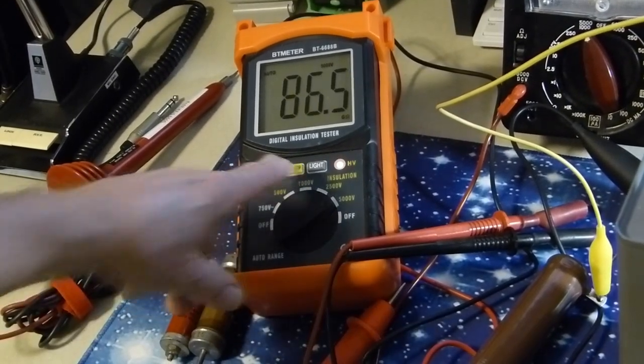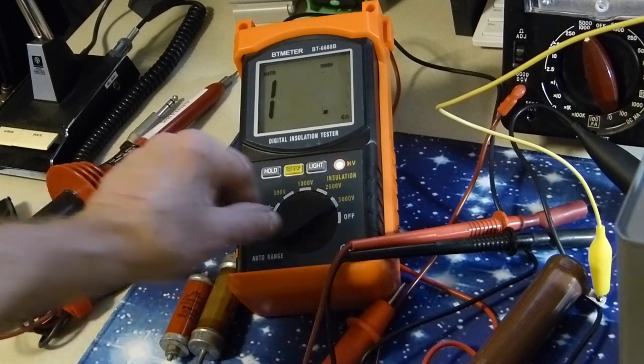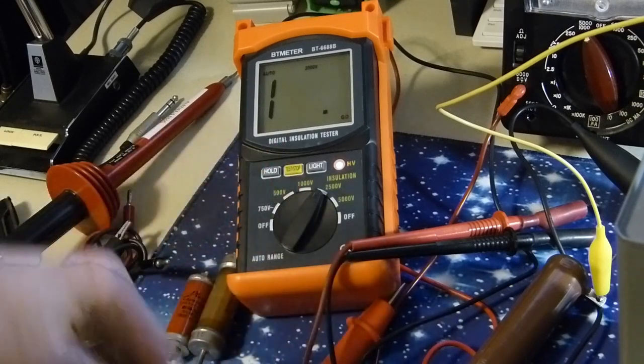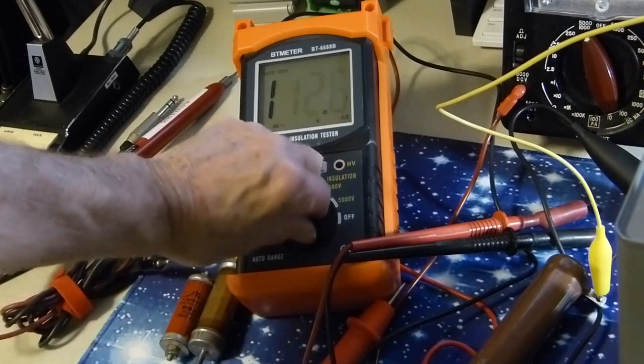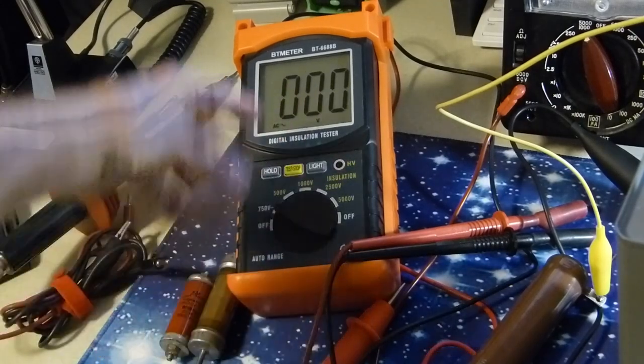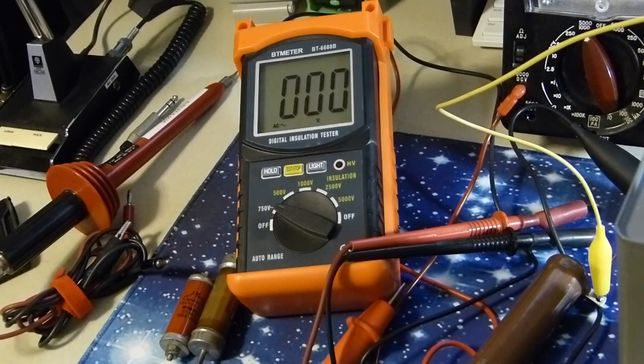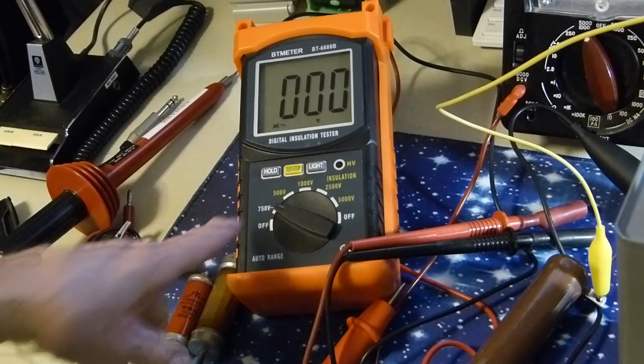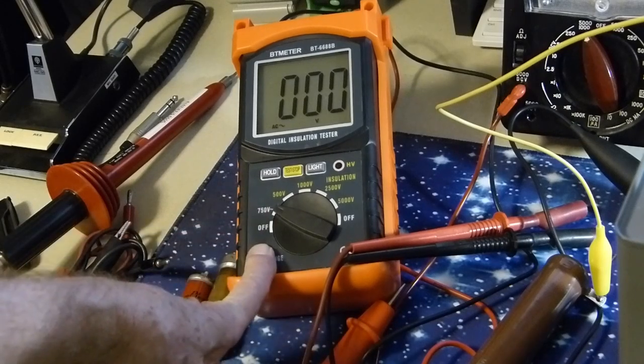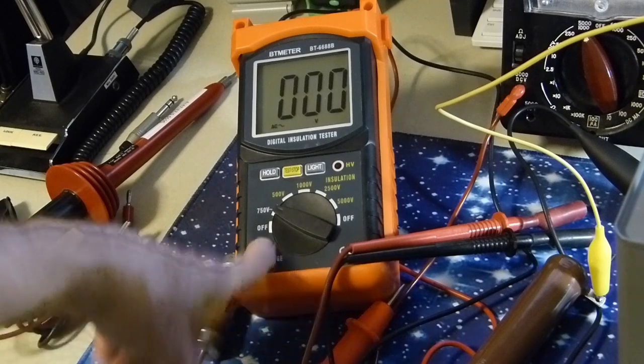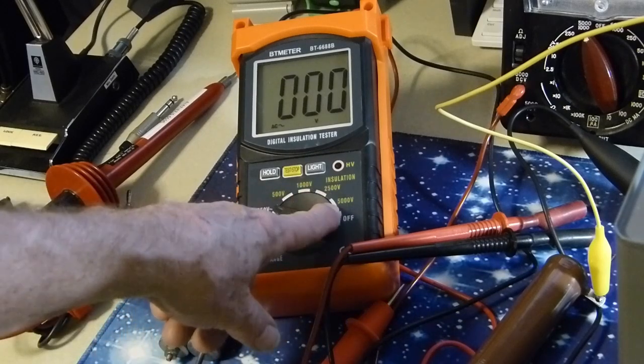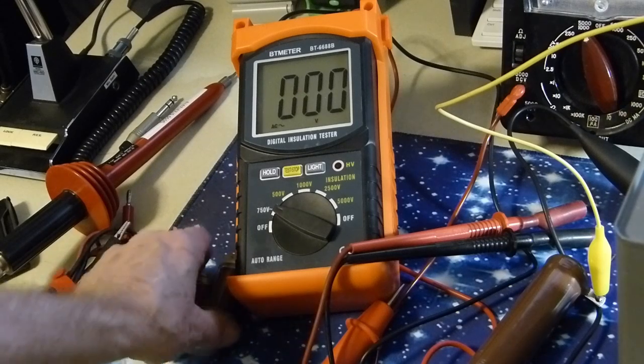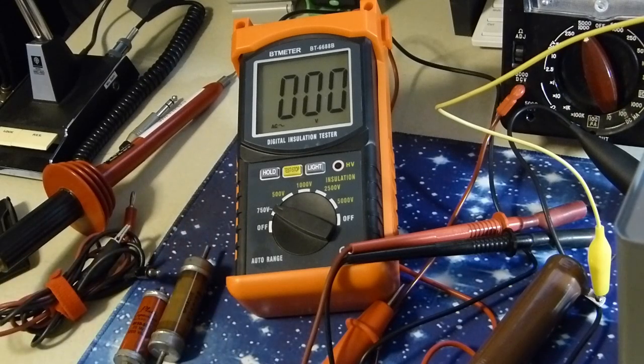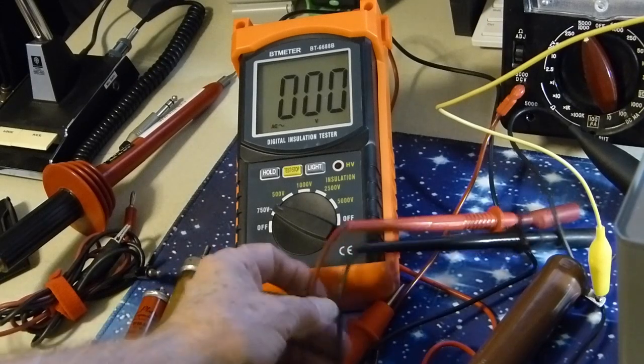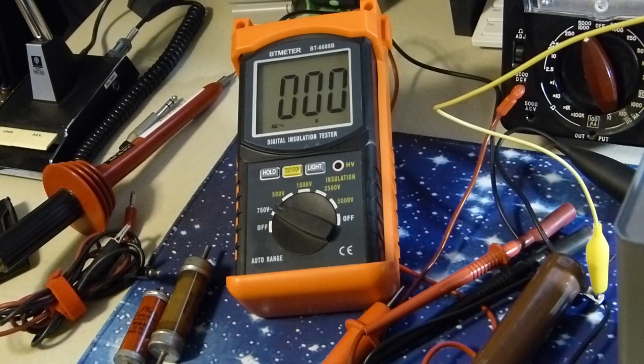You just turn it on and you've got that voltage out there, up to 5 kilovolts, with a one milliamp dead short. So if you pick it up, it's probably going to bite you. It's also got a 750 volt AC scale, so you can measure the 120 coming out of your wall, or 240, that kind of stuff. So on any of these scales, 500, 2,500, or 5,000, with a dead short current of 1 milliamp, it's probably just going to bite you pretty good, like a static discharge from walking across the rug. I don't think 1 milliamp is going to be very harmful, but...